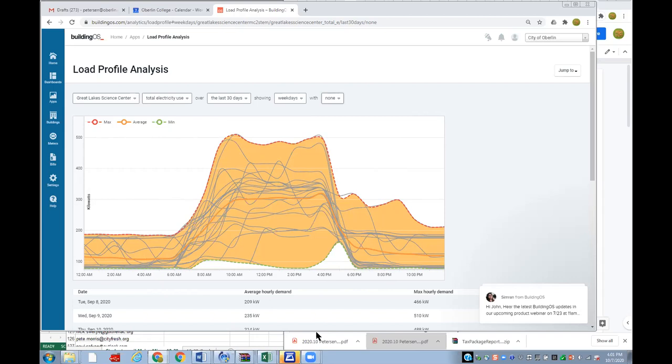This is often really helpful for understanding building management, because patterns that recur every day at the same time tend to be indicative of management as opposed to human behavior. You can see this really characteristic drop off between 4 and 5 p.m., or 4 and 6 p.m., where almost every day there is this steep drop off in energy use, and then it's much more consistent.